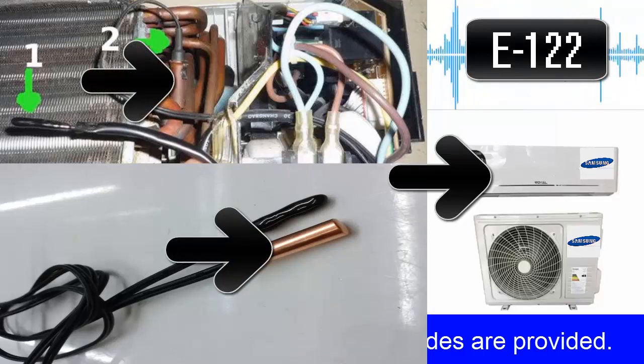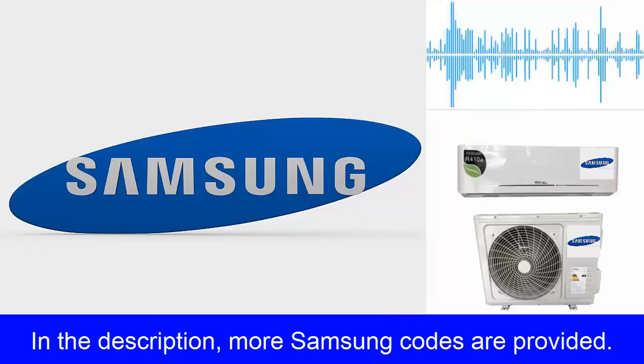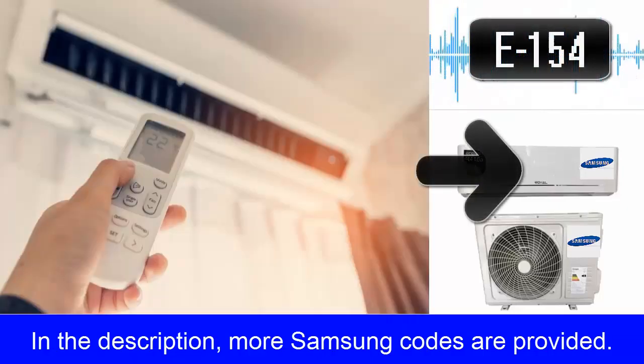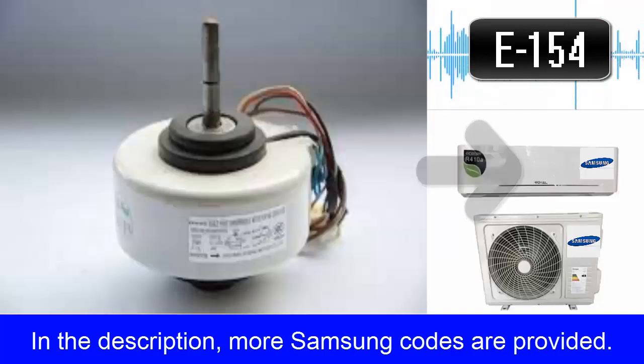4. Fault represented by error code E154. It is related to issues with the fan located in the indoor unit. A. Examine the fan's condition and its connection. B. Check the fan capacitor. C. Inspect the fan bearings.